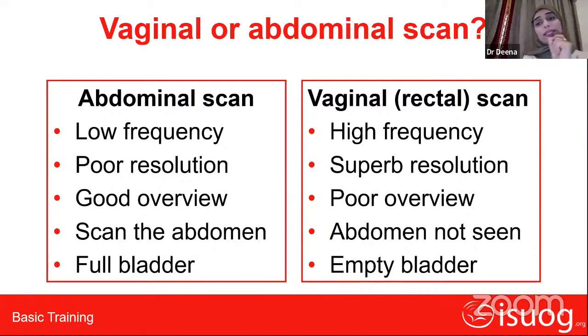On the other hand, for the vaginal examination, some people also use rectal scanning for virgin patients. For transvaginal scanning, you need a very high frequency probe. That's the endovaginal probe, and it ranges between 4 to 9 or 5 to 9 megahertz. That gives a superb resolution because the frequency is high. The higher the frequency, the higher the resolution. And you don't need low frequency in such an examination, because you have a very small field, just one ovary, two ovaries and one uterus. So you don't really need that much depth. That's why you have superb resolution with a high frequency probe, but a poor overview.